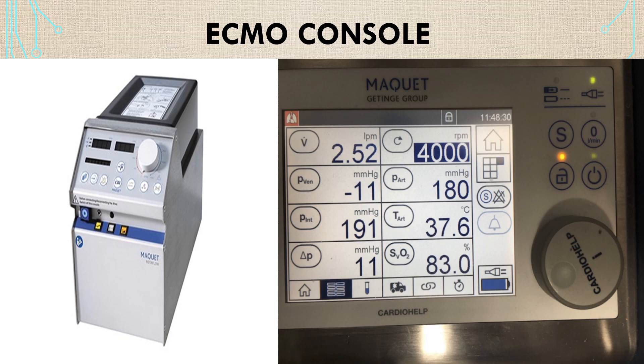In modern ECMO consoles, integrated circuit monitoring and safety capabilities are provided, including pressure circuit monitoring, bubble detection, a comprehensive alarm system, and servo regulation of the pump when a problem is detected.